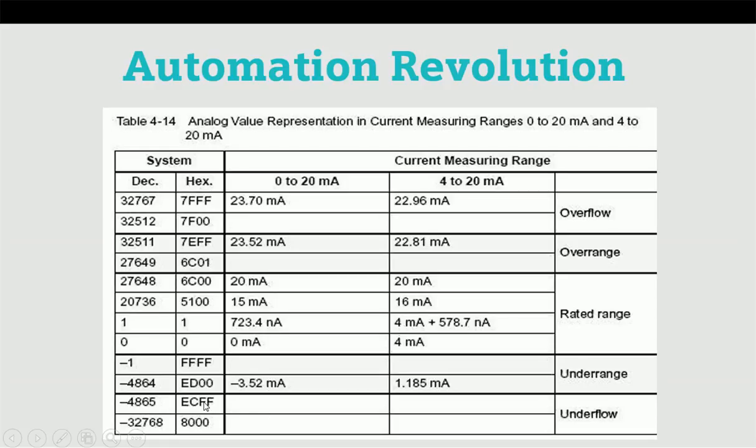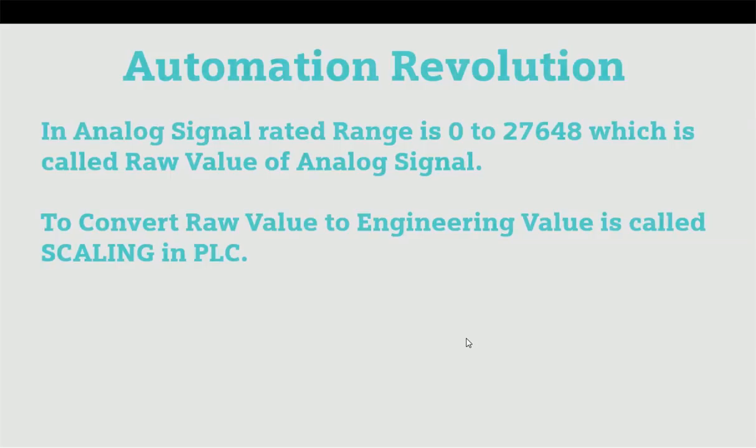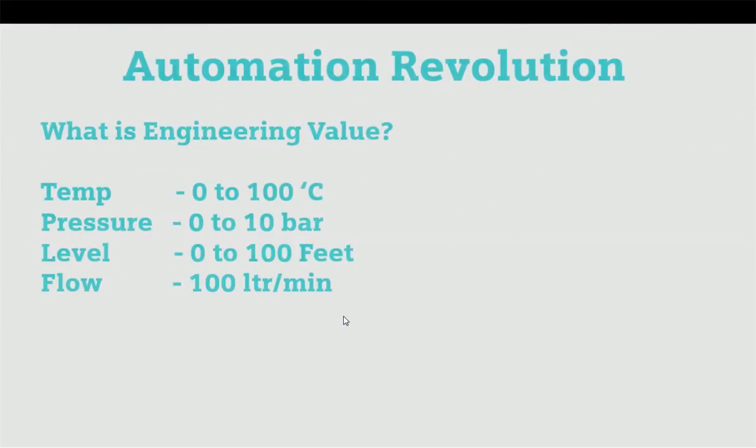What is engineering value? It's a unit range that any technical person or engineer is able to understand. If we are talking about temperature, we understand 0 to 100 degrees Celsius or 0 to 1000 degrees Celsius. For pressure it will be 0 to 10 bar, for level 0 to 100 feet, for flow 100 liters per minute. We understand this engineering value, not decimal or binary language. So we are converting this raw value into engineering value. This is what we call scaling.